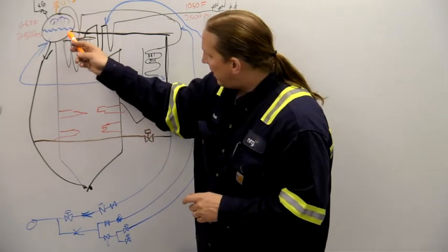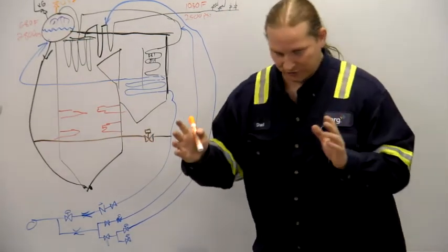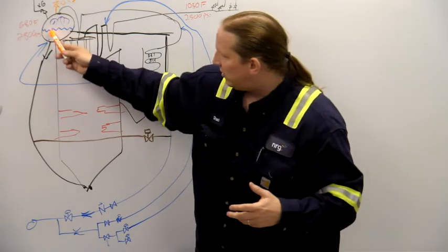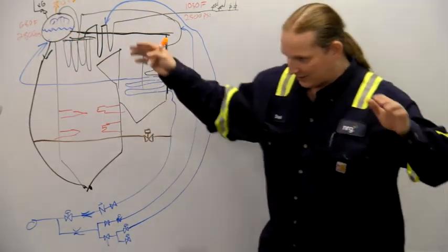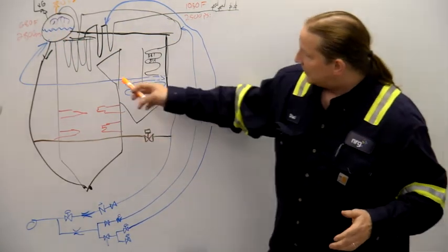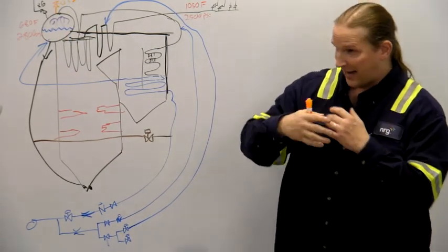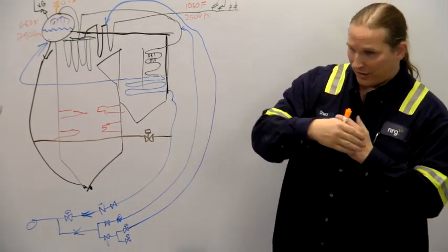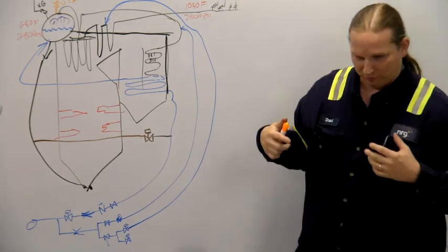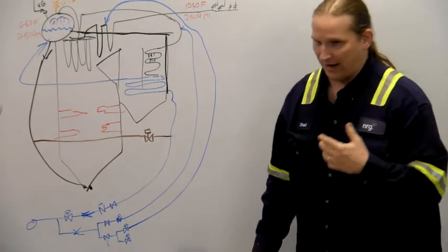What you're worried about is that you're obviously heating the inside of the drum and not the outside, right? The outside is exposed to the air. The inside has this hot water going across it. And if the inside expands and the outside hasn't expanded yet, then you get a pressure pushing out that can cause stress fractures and make your drum not last as long.